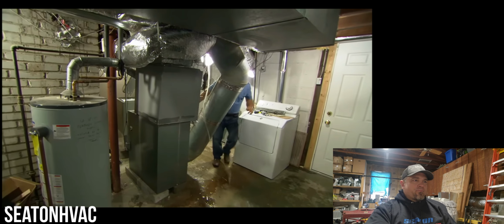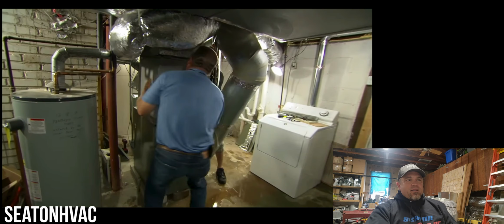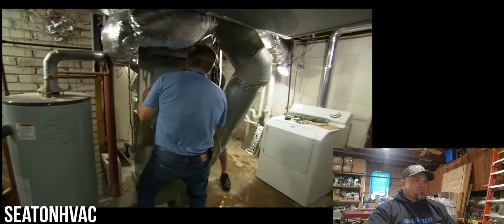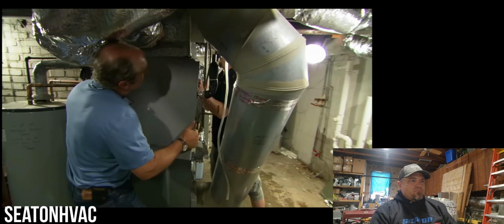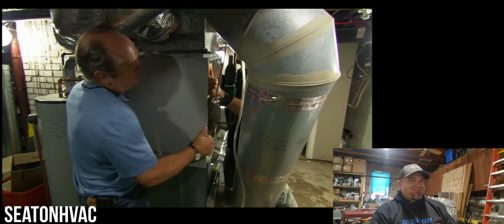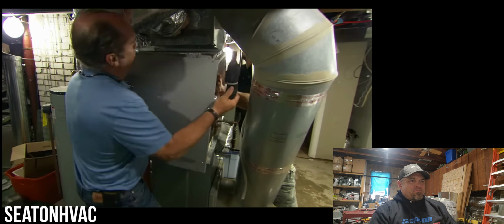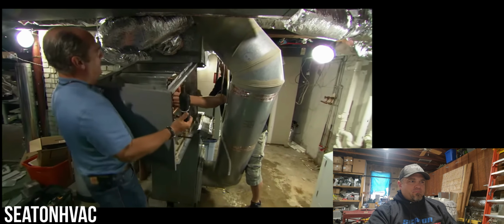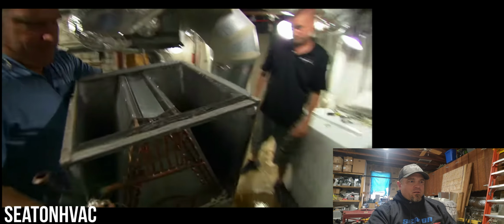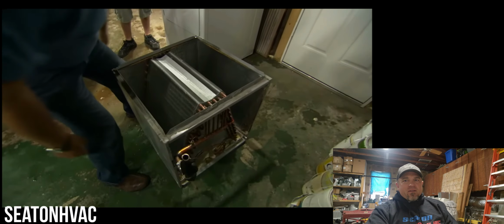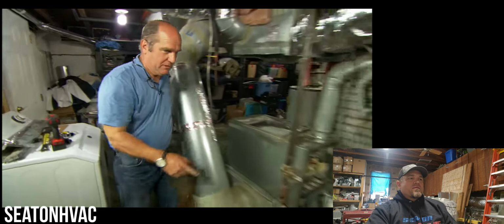All right, good. Why don't you come right to here? Let's see if we can muscle this out of the way. You can't. Look at that coil sits on there. There's like a couple inches on either side of it that aren't even in the airstream. You can get away with that with an A coil, and it won't ice up on you if it's sized right. But come on, guys. Be careful. There's sharp edges on this metal. Okay, I got it. You stay clear, it's sharp. I'll drop it right down. Bye-bye, 4-ton. All right, so let's get this one into position.